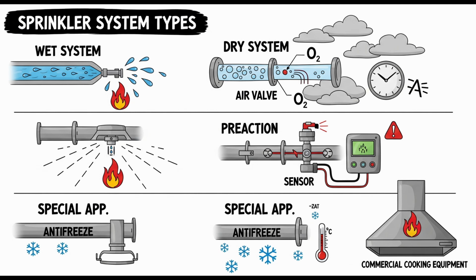the main system piping. It's truly incredible, the level of detail, how deeply the standard goes into addressing every potential challenge, every specific environment. From preventing a minuscule ice plug in a freezer pipe with a cleverly designed removable section in dry air, to specifying the exact temperature rating of a sprinkler head positioned just inches above a blazing hot commercial fryer, to ensuring fire won't easily wrap around the corner of an exposed building by requiring extra heads or linked check valves. Every single detail, down to the precise diameter of a hole you can barely see in a valve clapper, clearly has a critical engineering purpose behind it, all aimed at ensuring the system functions reliably and effectively when it's needed most. Absolutely.